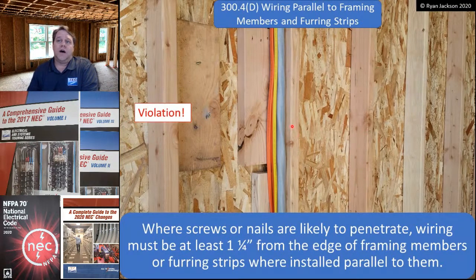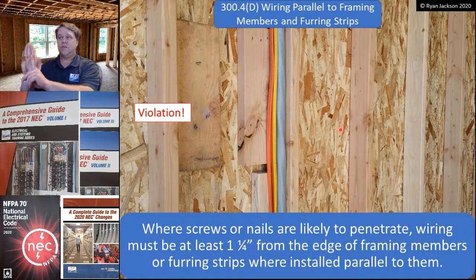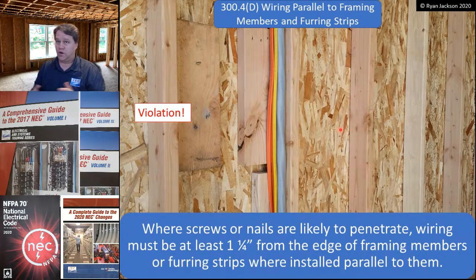If the drywall guy can miss hitting a stud, and a lot of us have hung drywall in our basements or whatever, you don't always hit the stud. Sometimes you miss. If that happens and you go right into the cable, well, that's a problem. So we do require 1 1/4 inches separation. It has to be back from the face. So if this is my stud, it has to be back at least 1 1/4 inches or away 1 1/4 inches. One or the other. Either way, it's got to be away from it at least 1 1/4 inches.